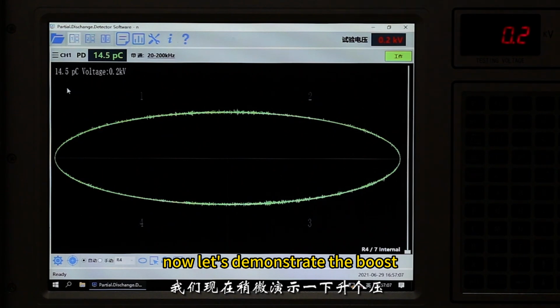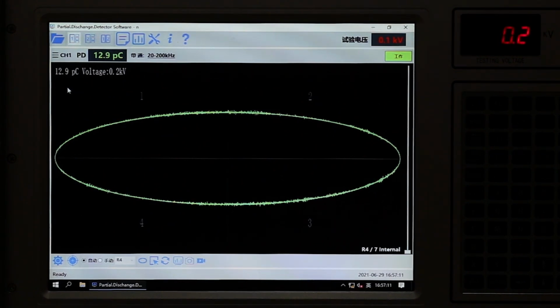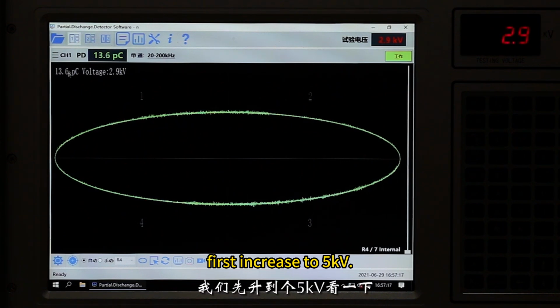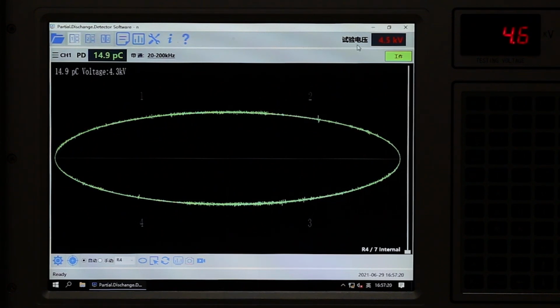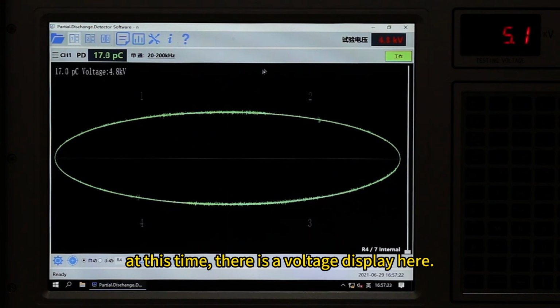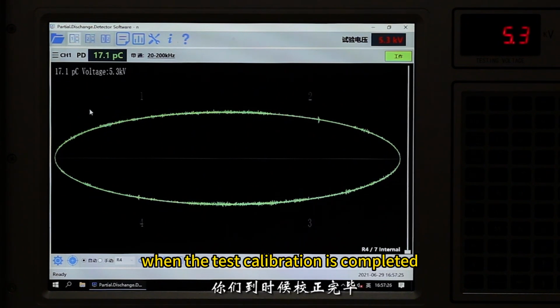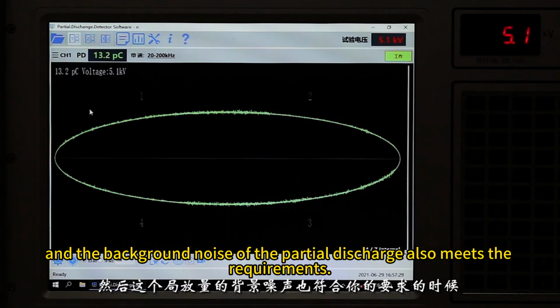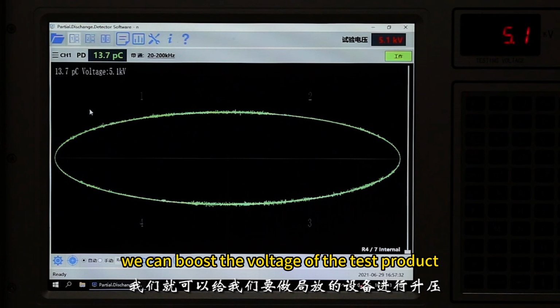Now let's demonstrate the boost. First increase to 5 kilovolts. At this time, there is a voltage display here. When the test calibration is completed, and the background noise of the partial discharge also meets the requirements, we can boost the voltage of the test product.